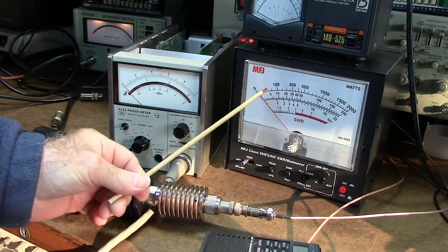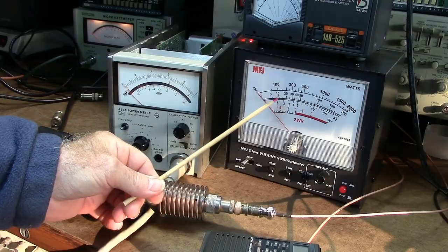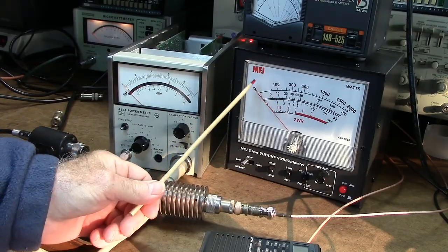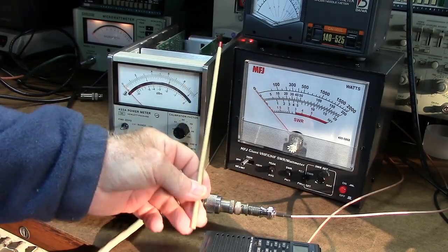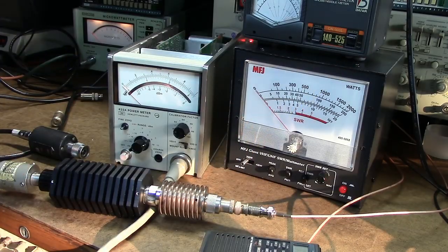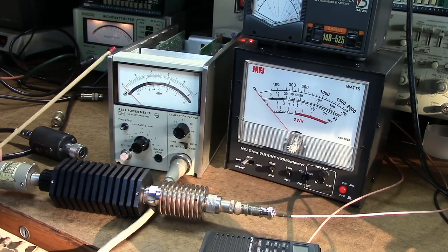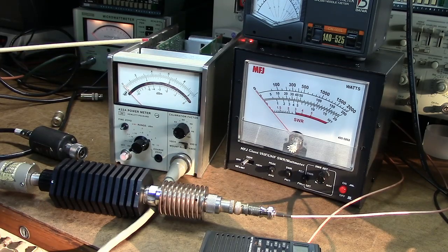accuracy. In fact, measuring at the lower part of an analog meter isn't the most accurate. You always want to measure in the upper 2/3 if you can. So anyway, this is working here. What I'd like to do to calibrate this is find somebody that has an accurate standard I can calibrate this against, and then I can use this to calibrate all my other instruments, including different watt meters, this microwatt meter, etc.